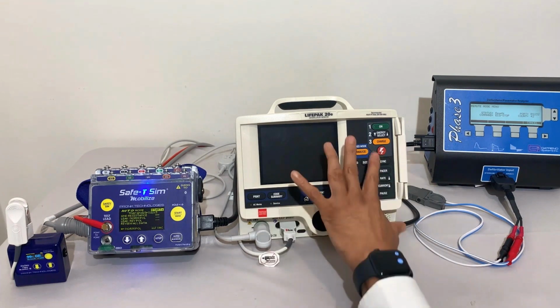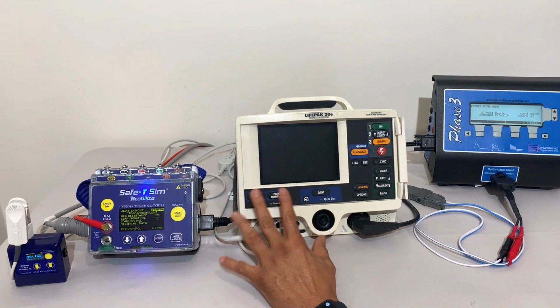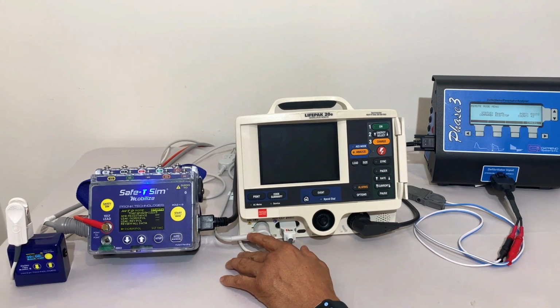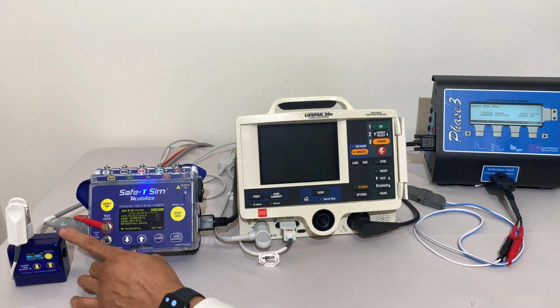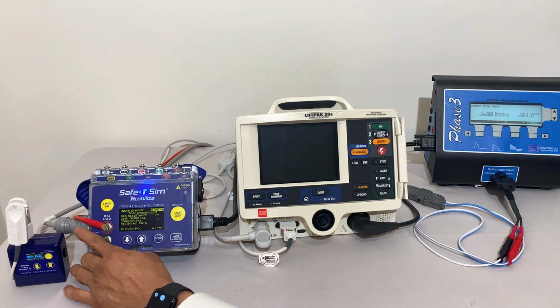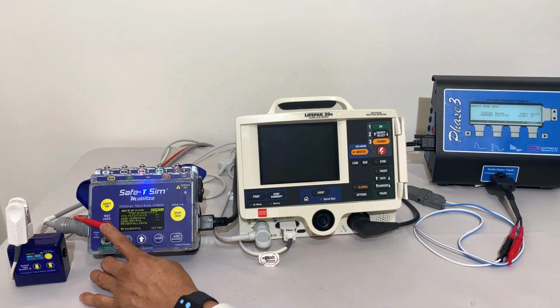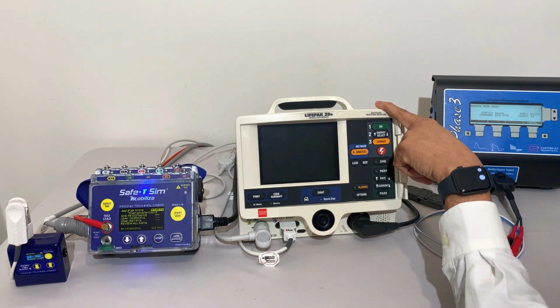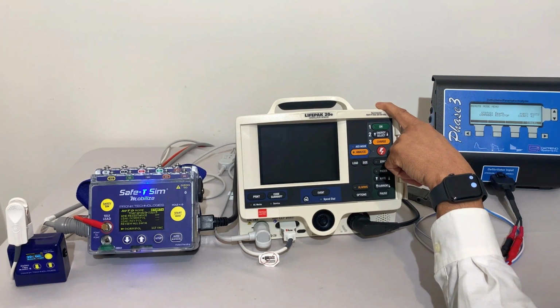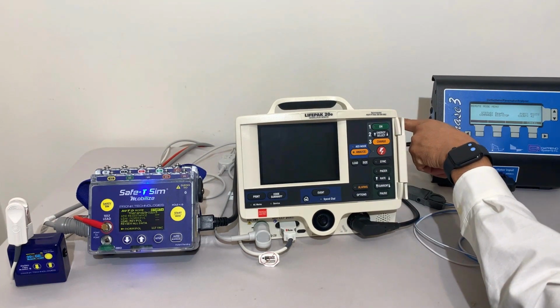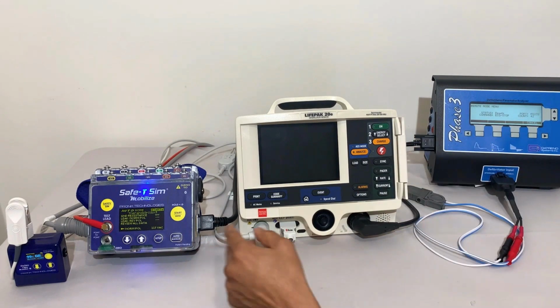Once we feel confident we physically inspected it, everything looks like it's in the correct order, we want to go ahead and connect it up to our test equipment. In this case, we connected the defibrillator up to the electrical safety analyzer. Here on the left, we plugged it into it. We've connected the red, what we call red test lead cable, to the back of the defibrillator for important leakage testing we need to do. It's connected to the ground post on the back of the unit. Of course, we've powered up the safety analyzer as well.